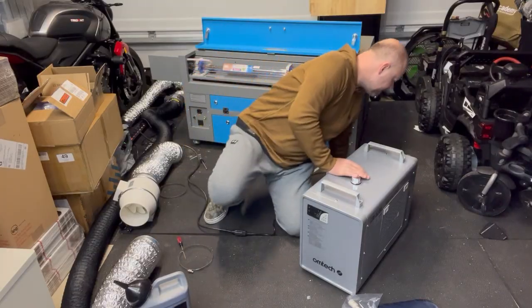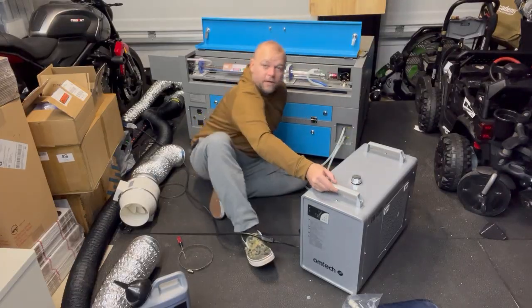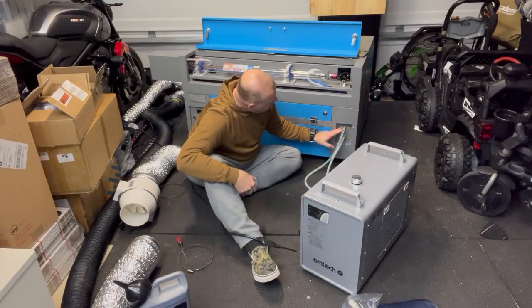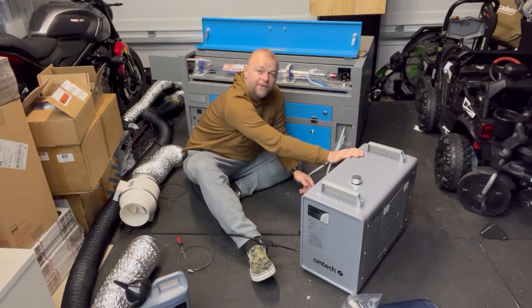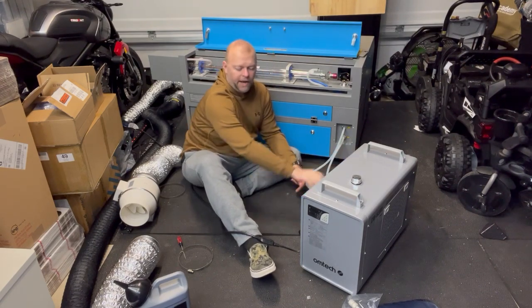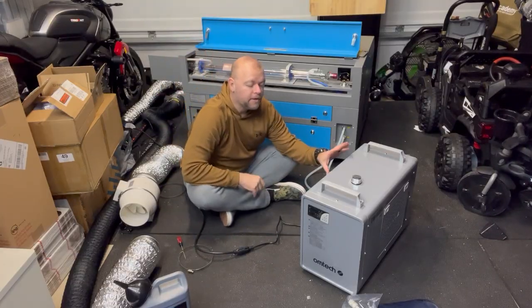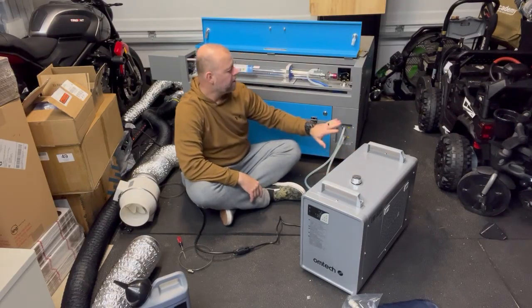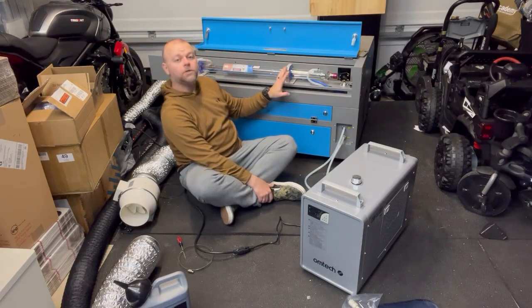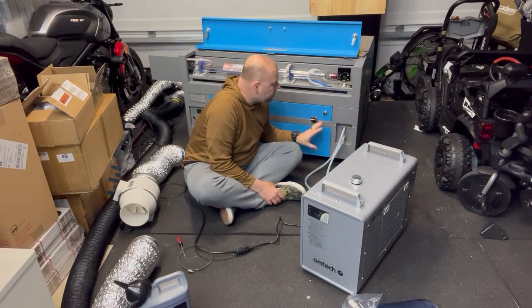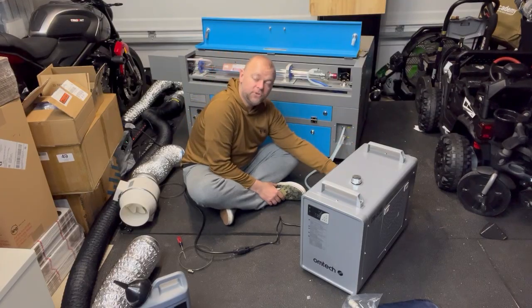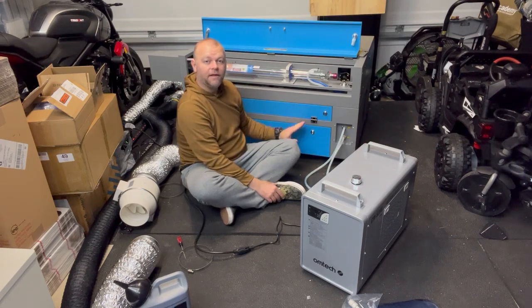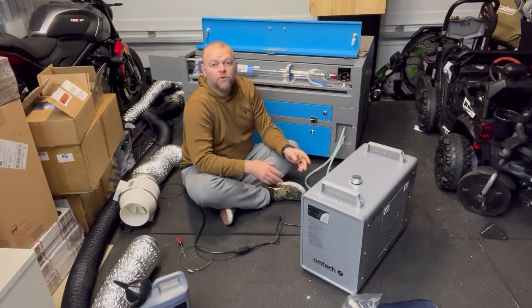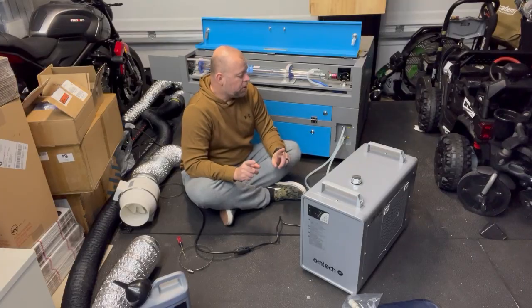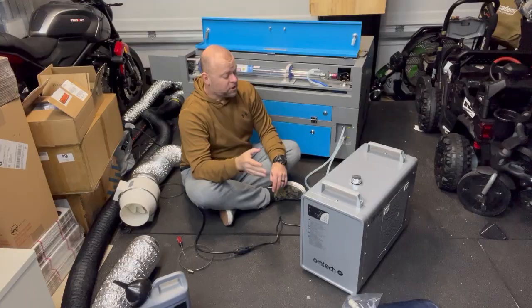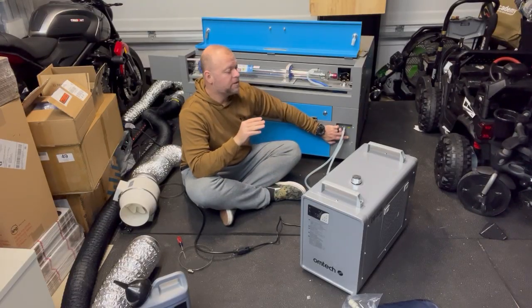So the biggest thing when you get your machine and hook it up: when you look at the back of the machine, you have a water inlet and a water outlet, and on the back of your chiller you have an outlet and an inlet. The best way to think of this is you want your chilled fluid going out of your chiller into your machine. It flows through the tube, warms up, and that warm water flows out of your machine into your chiller. So out to in, out to in - that's the easiest way to make sure you have your hoses flowing correctly: out of the chiller to the in on the machine, out of the machine to the in on the chiller.